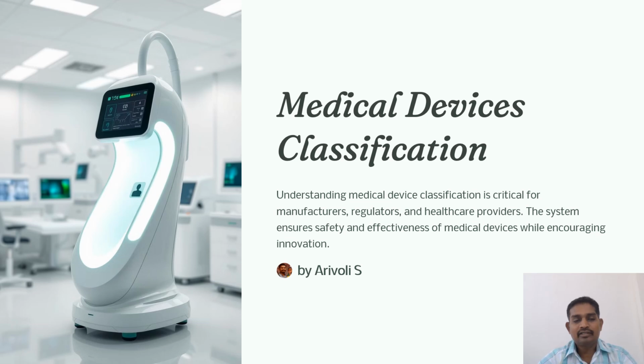So the criteria are the duration of contact with the body, degree of invasiveness, local versus systemic effect, potential toxicity, dependence on source of energy, and part of body affected by the use of the device. So these are the various set of criteria that have to be considered for classification of medical devices.